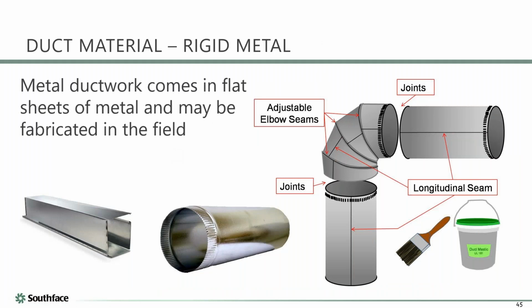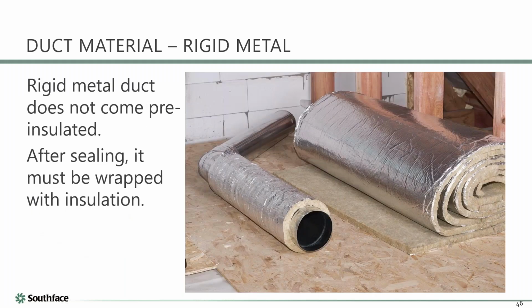So in a little more detail, metal ductwork is the smoothest, least resistant conduit for making air move. Any kind of fluid moves the smoothest in a straight round metal duct. And what's good about it is it's very durable. It requires you to actually usually do a design and think about where things are going to run. It's got a lot of good things going for it. It's also expensive. It also has lots and lots of leak seams that need to be sealed with mastic. You got to screw it together. It's certainly the most expensive duct system out there. And it doesn't come with insulation. So on top of everything else, you got to wrap it with insulation.